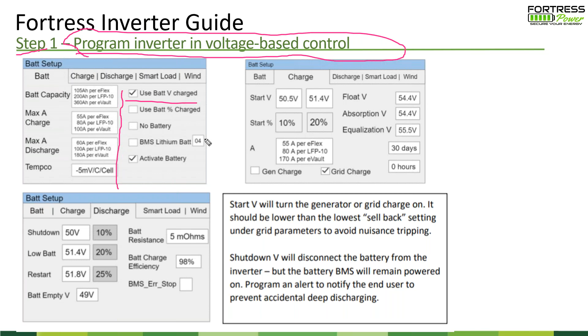Now, if you think the battery management system will remote program the inverter, yes, there is some of that, but programming the voltage-based controls, particularly with the Sol-Ark inverter, is quick and easy. Just press the battery setup menu and plug in the values from the inverter integration guide using voltage-based controls, not enabling the battery, not enabling the percent charge. We'll come back to that. That'll get you up and running.